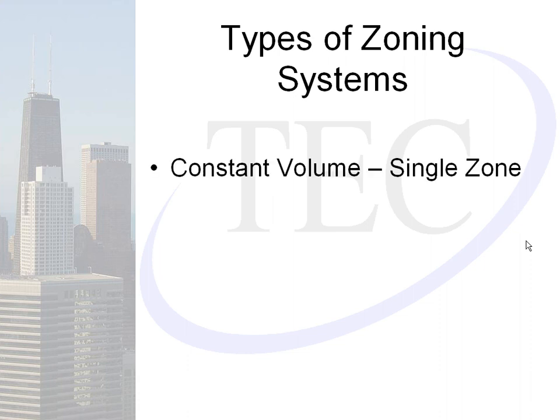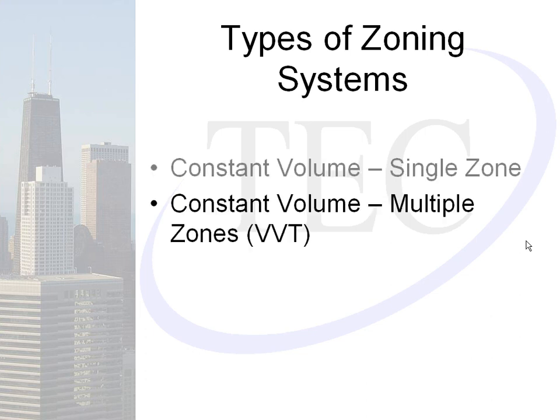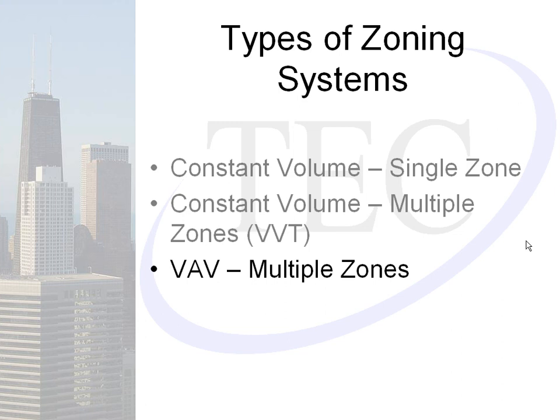There are three distinct types of zoning systems. The first type is constant volume single zone, most commonly seen as a rooftop unit. We then have constant volume multiple zones, which is better known as VVT. And we have VAV multiple zones. The primary difference between constant volume and VAV is that constant volume has the fan running at a single constant speed, while the VAV unit's fan speed or vortex dampers adjust according to static pressure in the duct, giving a variable volume of air.